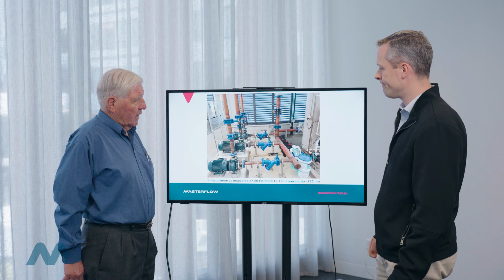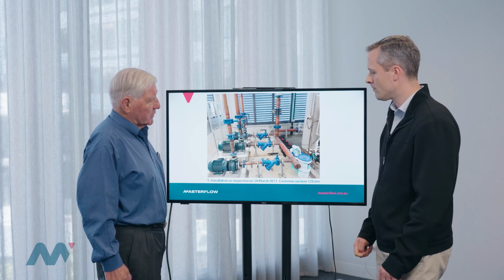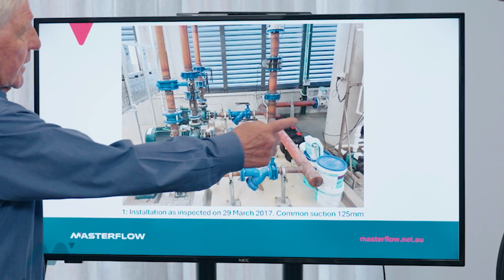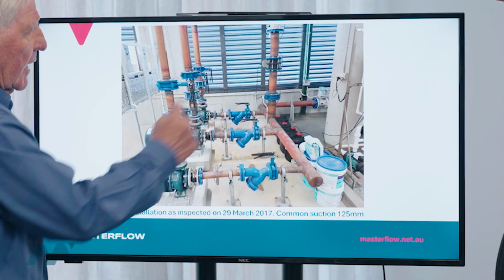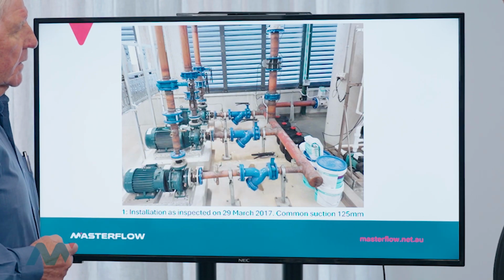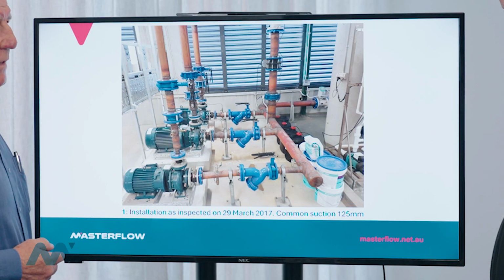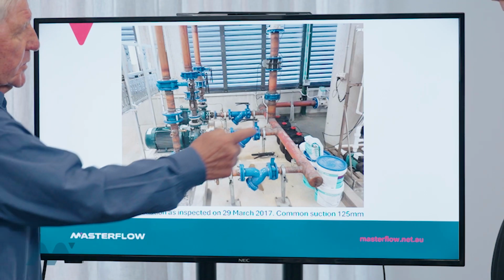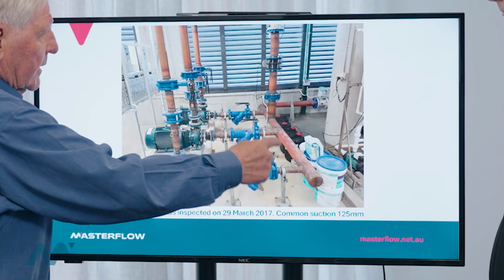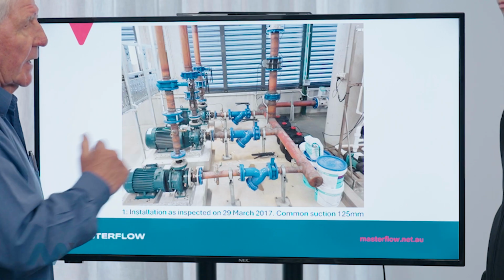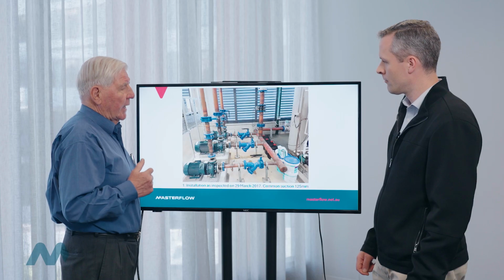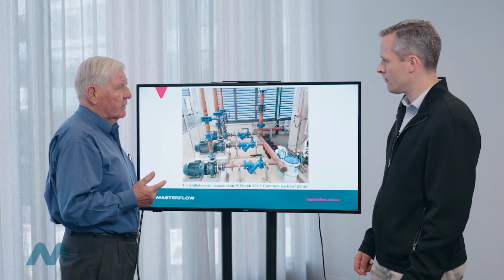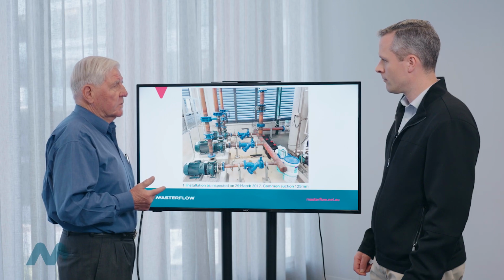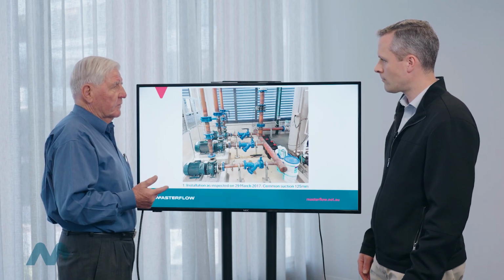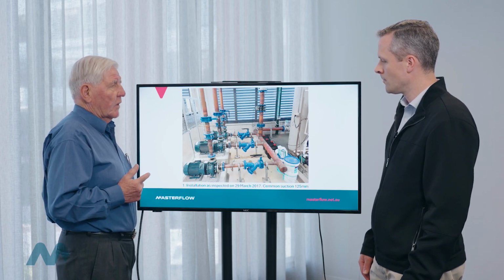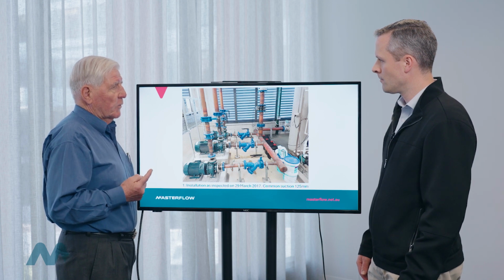Yeah, well, I guess I've got questions about the suction manifold. And you can see that the suction manifold here is a larger diameter than the branches that are going into the pump suctions. So there's potential for trapped air in that part of the suction line unless you can bleed the air out of it. And if you've got air trapped in that manifold, that will affect pump performance and you expect the pump to underperform as a result of that trapped air in the suction line. So that's point number 1.